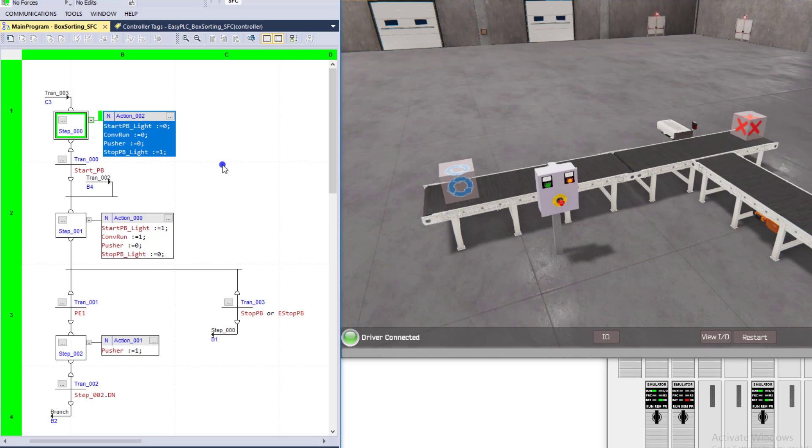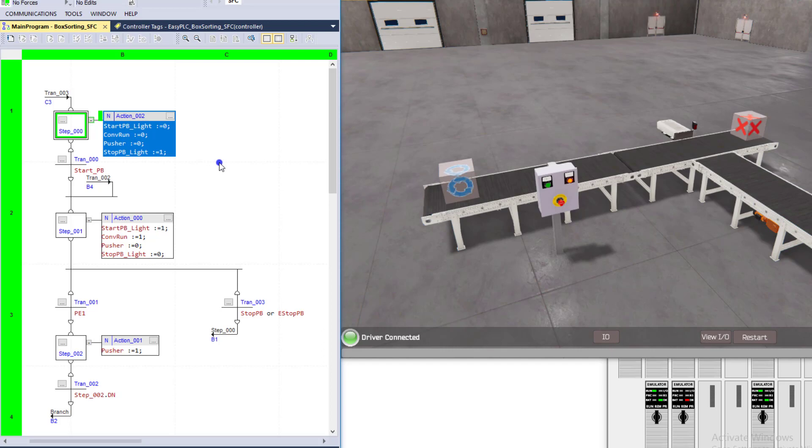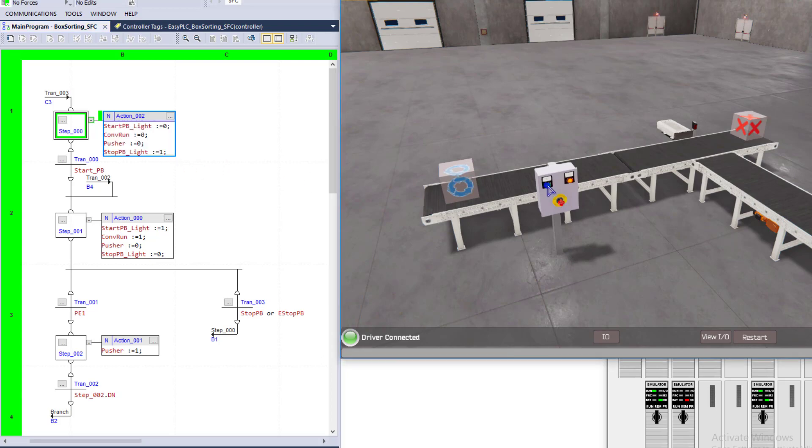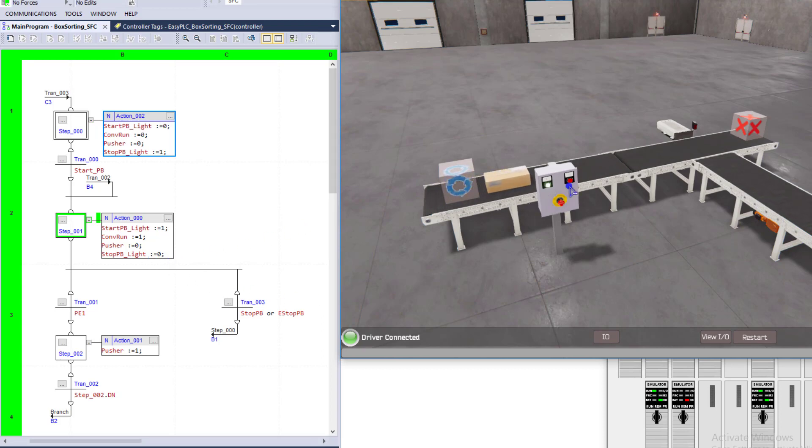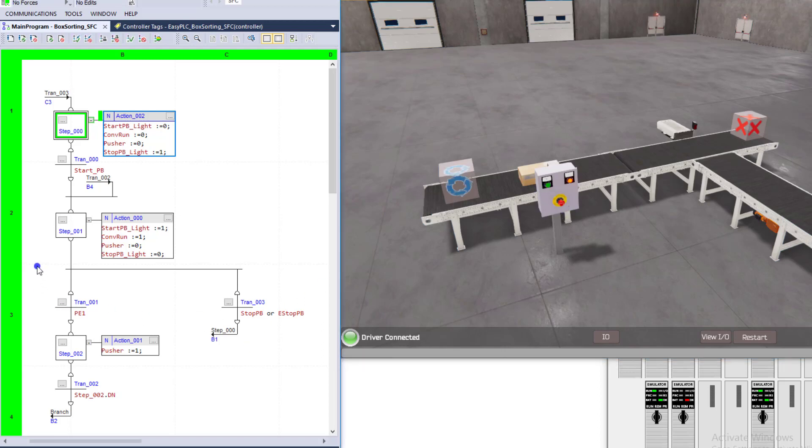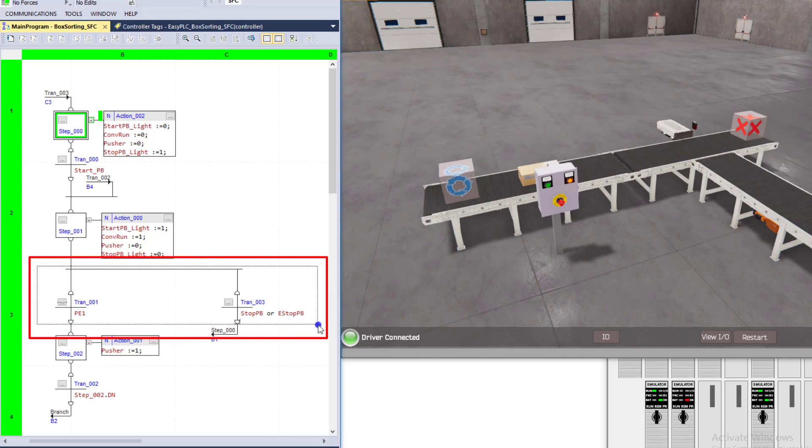Now keep in mind when you're doing sequential function charts, if you write a tag into a value of one, make sure you write it into a safe state, whatever safe state it is deemed in your system in a controlled manner. In my case, if I write the start or a tag of one right here, if I start it, I'm writing that tag a value of zero right here. If I want to stop the whole system, I can hit the E stop and it will E stop the system as well.